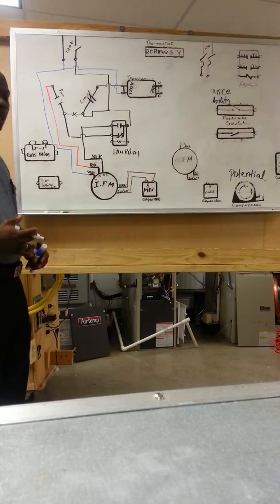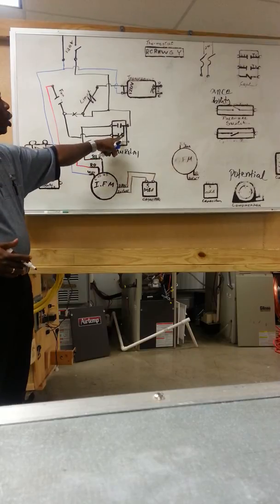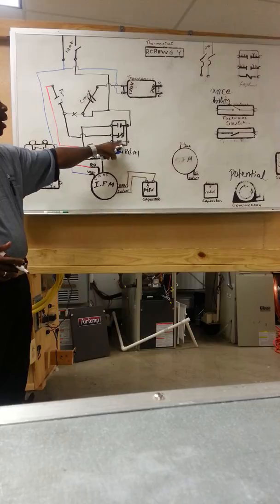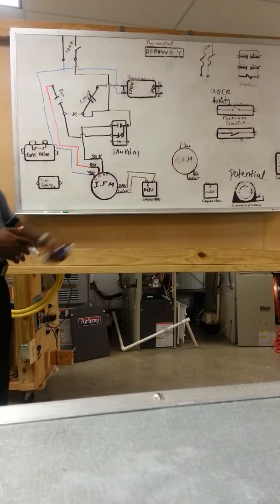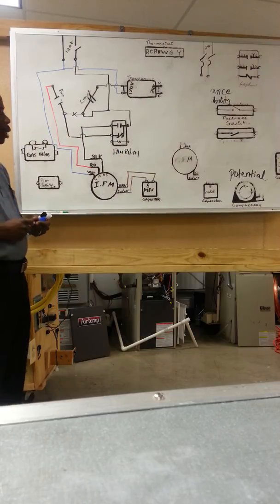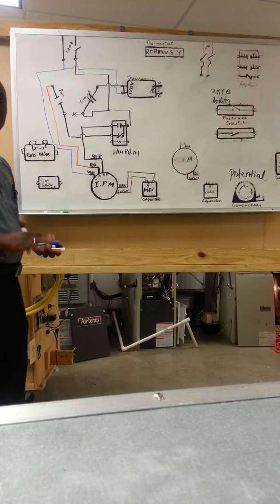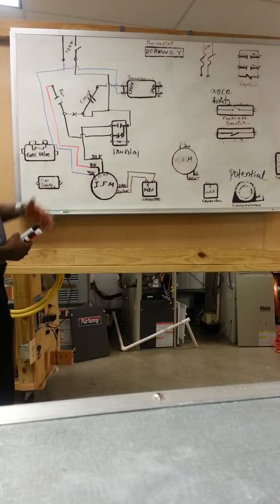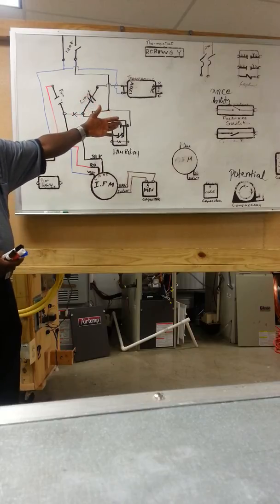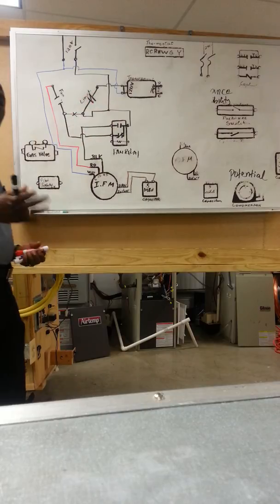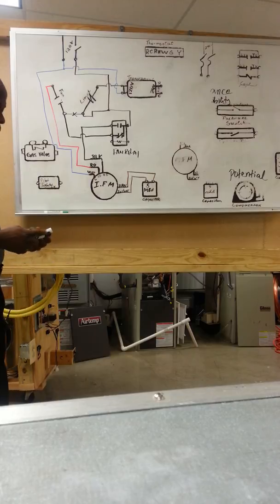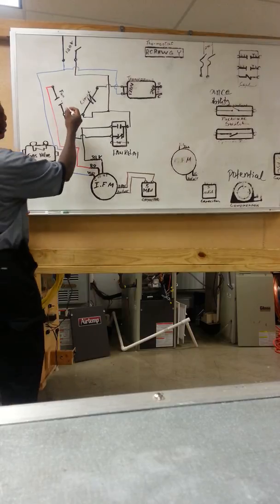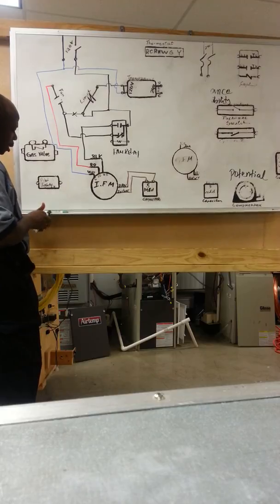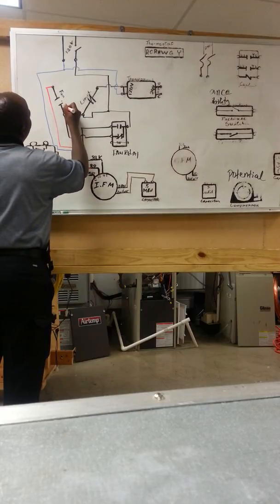Once this relay contact energizes, it will close this normally open side and open the normally closed side, and then the fan will come on high speed for cooling. Now for heating though, this relay is not going to do anything with the fan. What happens once the burner comes on, the burner is going to burn and create a temperature of about 150 degrees Fahrenheit inside here. I'm going to use a red marker here. 150 degrees Fahrenheit in the fan center.